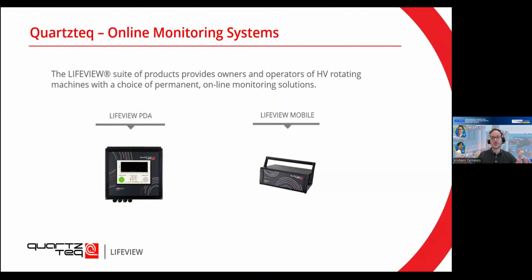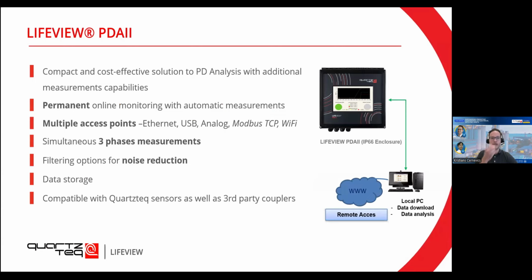So it's not installed permanently, but it still needs the installation of the sensors on the machine. So you could have multiple machines with sensors, and then with LifeView mobile, you go there periodically and measure the discharges. With the PDA2, you can measure continuously. So it's always on, it always gathers the data. So it gives you a bit better representation and doesn't need the movement of the equipment. So the PDA2 is essentially a small computer that you can put somewhere near the machine. It's a permanent online monitoring system with automatic measurements. So periodically, automatic measurements are going to happen every couple of hours.